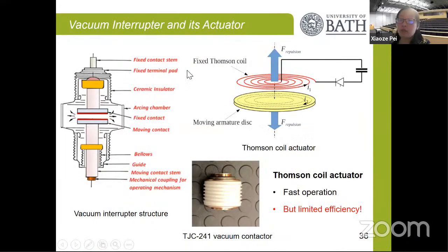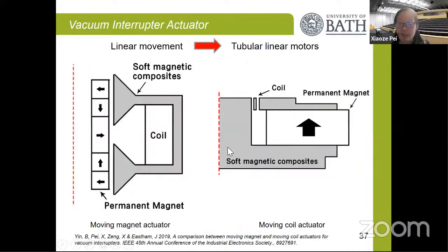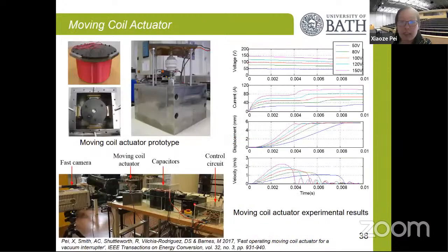Besides this, we're also looking into the operating system for the mechanical switch, because the current research projects mainly use the Thomson coil, which is very fast in operation but has very limited efficiency. So what we have been looking into is a moving coil actuator, which is very similar to a loudspeaker. The permanent magnet creates a magnetic field, and the coil is suspended in the air gap. When we drive a current in the coil, it will have a Lorentz force going up or down, and the movement. Because we can design the coil to be very light, there is light movement and very high efficiency. So we built a prototype in the lab using the moving coil actuator, which is able to provide a displacement of 5 millimeters within 4 milliseconds, so very fast.